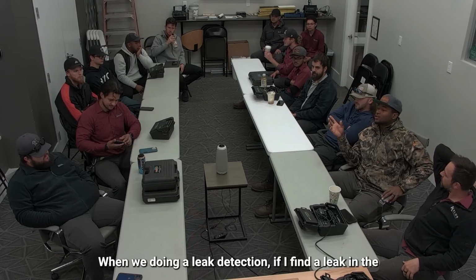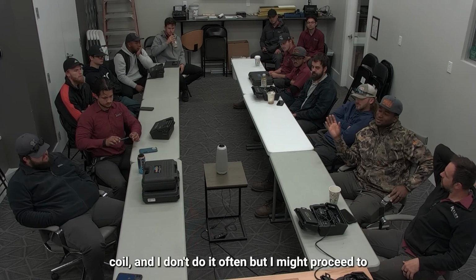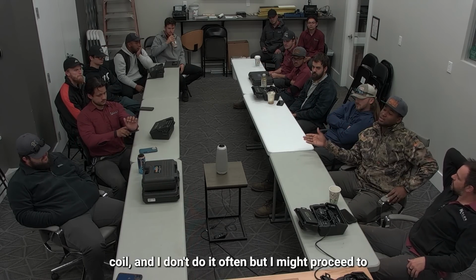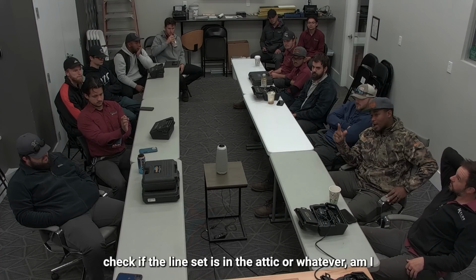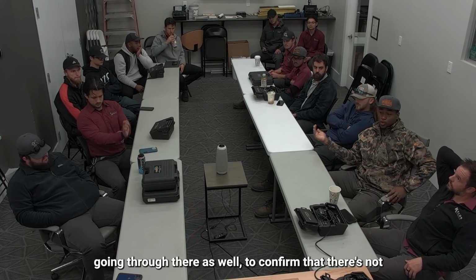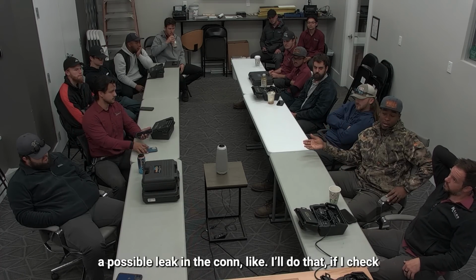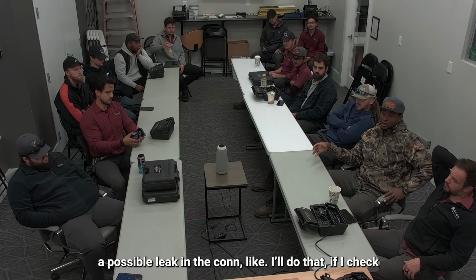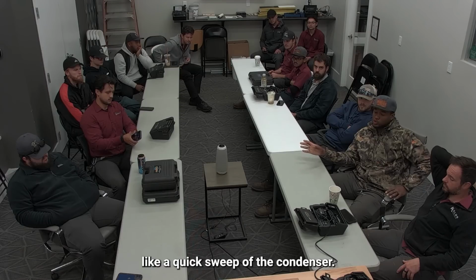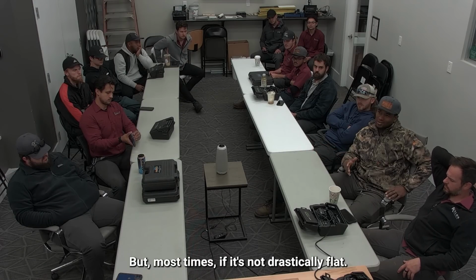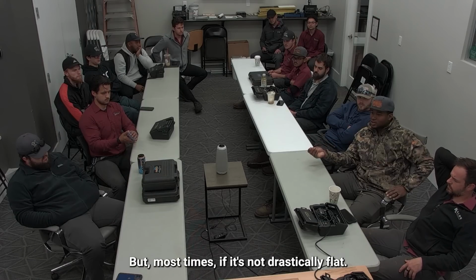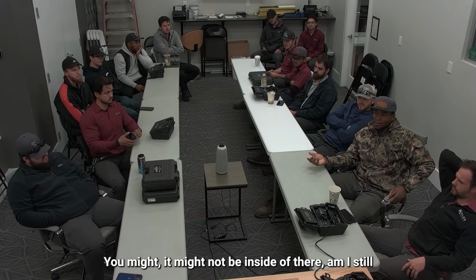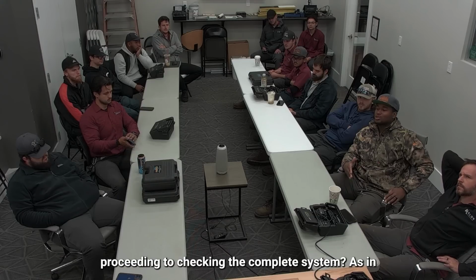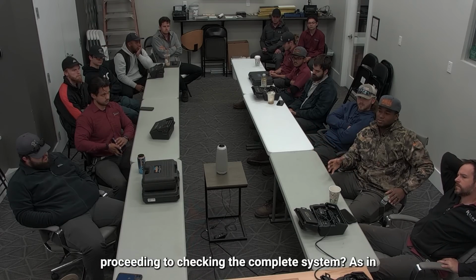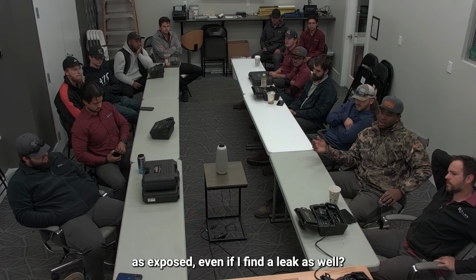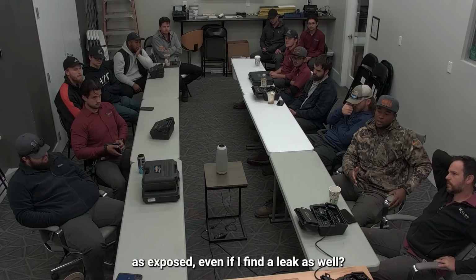When we're doing a leak detection, if I find a leak in the coil, I don't do it often, but I might proceed to check if the line set is in the attic or wherever. I'll go through there as well to confirm there's not a possible leak, and do a quick sweep of the condenser. Most times if it's not drastically flat, it might not be inside there. I might still proceed into checking the complete system, everything that's exposed, even if I find a leak.